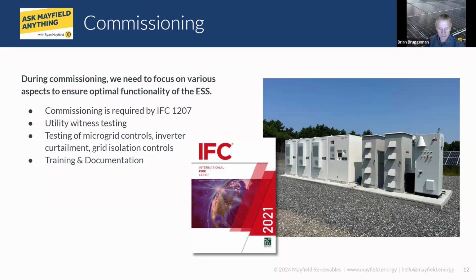It needs to be determined who's responsible for the different areas of the commissioning. Oftentimes the manufacturer will do some parts of it, the controls vendor will definitely do some parts of it, and the engineering team could do parts of it. The utility will also want to come out and most likely do a witness test at this point to make sure the system operates as it was designed and interconnects and disconnects from their grid appropriately.